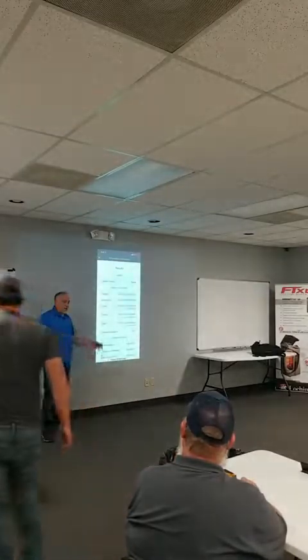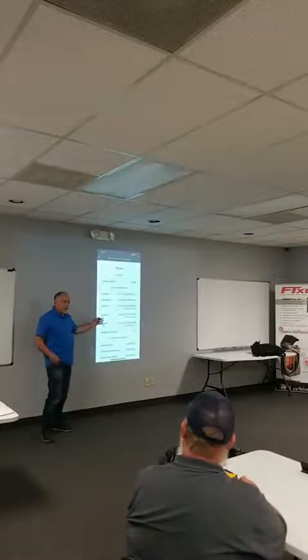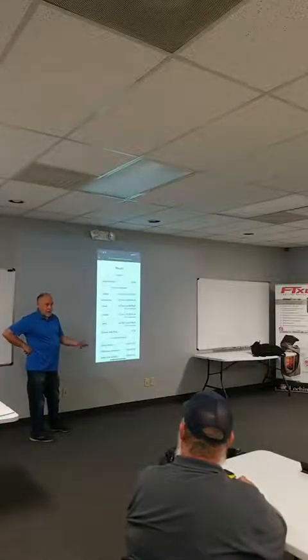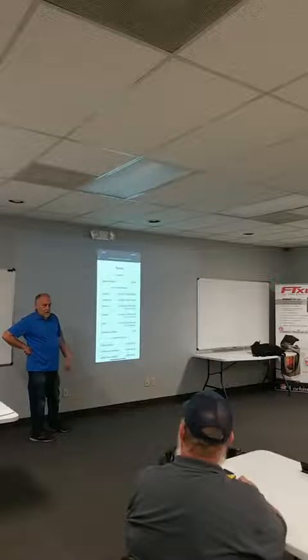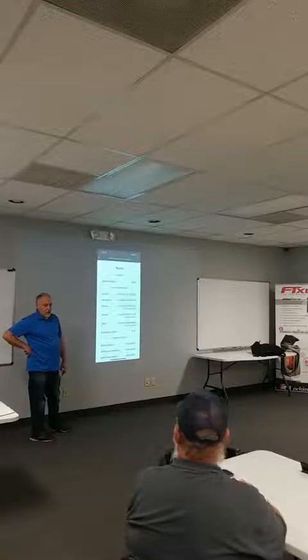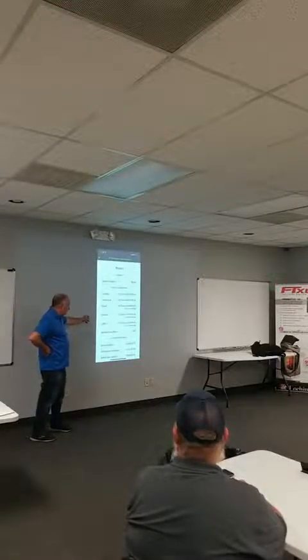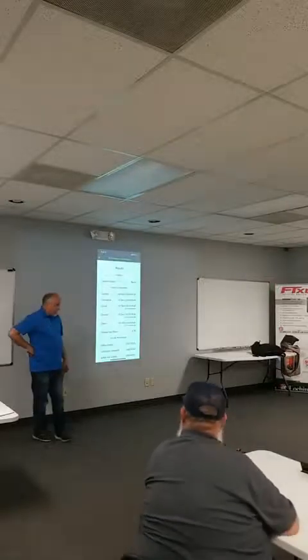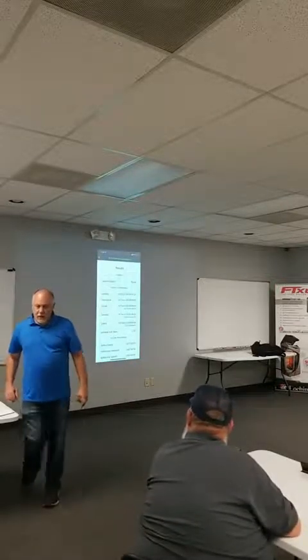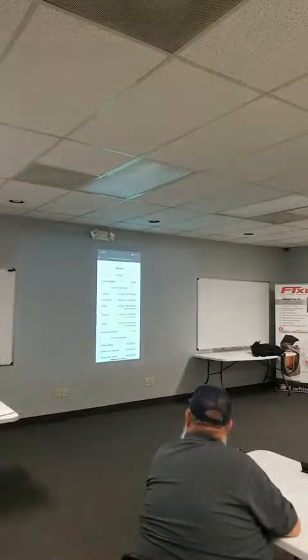Now, this would start to drop if it was hotter out in the shop. If we got up to like a 95-degree day, we don't have enough condensing space. Liquid line's going to go up, sensible capacity's going to drop. Right now it's running good because it doesn't have a lot of load. But that is what tells you the sign. The estimated airflow calculation on there is actually very accurate. We've compared this against NIST.